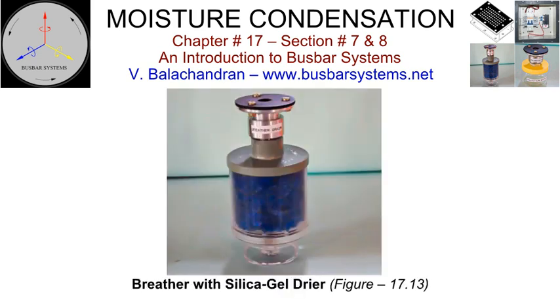Filters, breathers with silica gel. Breathers cum filters are installed on top of the bus enclosure. It enables it to expel or inhale air due to the variation of the temperature inside the enclosure. Sometimes, a container with dry silica gel is attached to prevent the ingress of moisture into the enclosure. Silica gel needs to be monitored for absorbed moisture content.